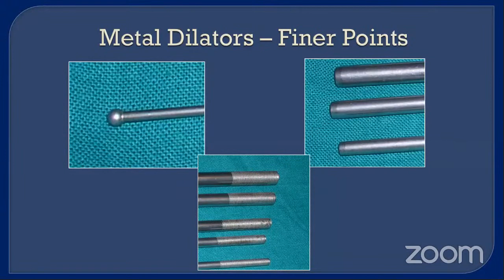Next set of dilators is called the single step dilator or screw dilator. Here you can see this is a single step dilator which has got a screw tip, and this works very well because it saves a lot of time, and this thing you can pass on after putting in the guide wire, where you can pass on the dilator straight away with the screwing movement, and over this the access sheath whichever you're using. This is mainly used in mini PCNL.